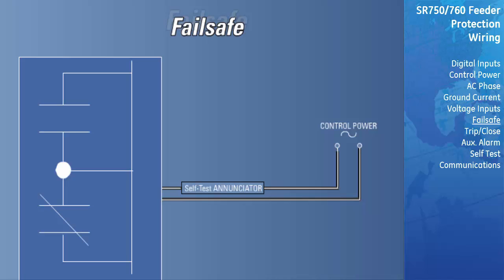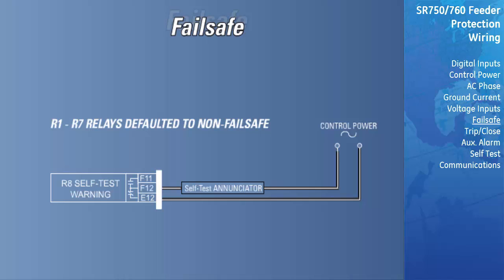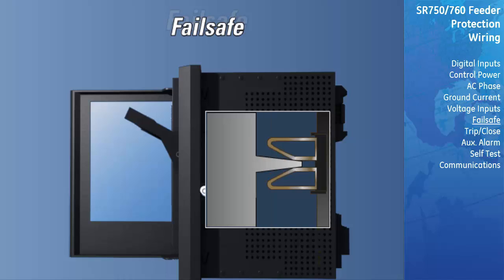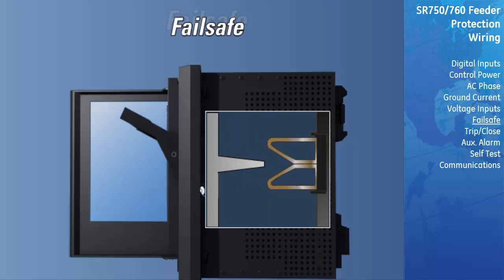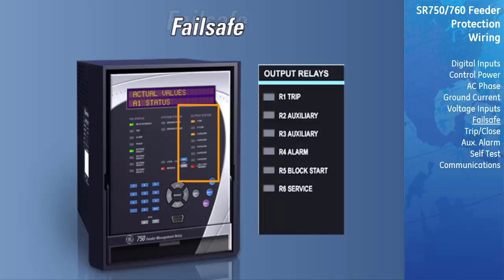The other 7 relays are defaulted to non-failsafe. They will normally be de-energized and will energize when called upon to operate. If failsafe operation is required from one of the auxiliary relays, their non-operated state can be programmed to energized. The trip and close cannot be programmed to operate as failsafe. Shorting bars in the drawout case ensure that no trip or alarm occurs when the relay is drawn out. However, any output relays that have been programmed as failsafe, including the self-test relay, will de-energize. Any device connected to the failsafe relay terminals will detect this change in state. An LED indicator on the front panel will light when the associated relay is in the operate state.